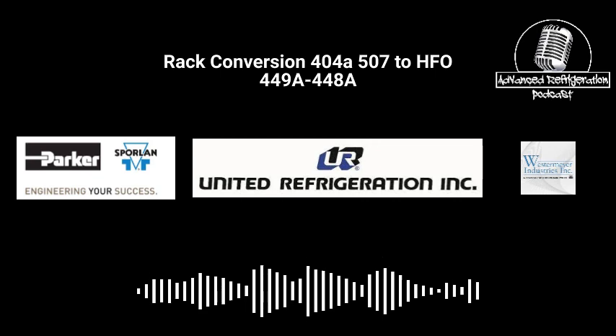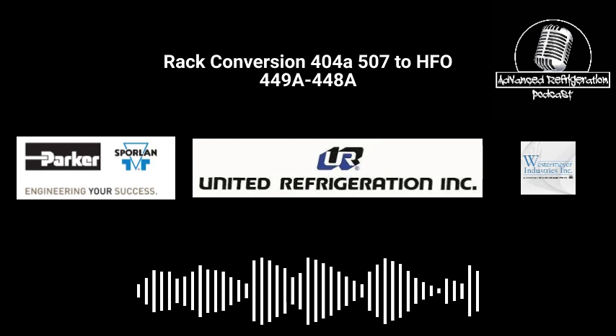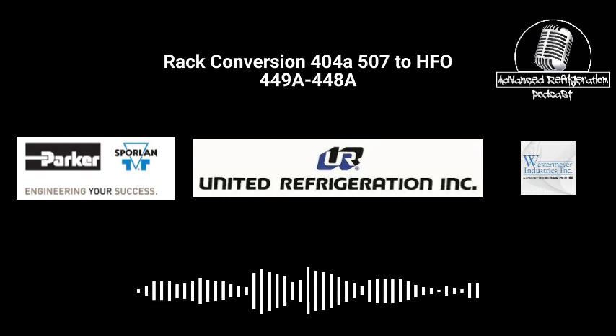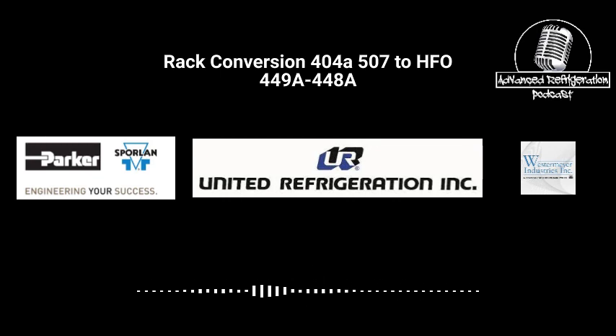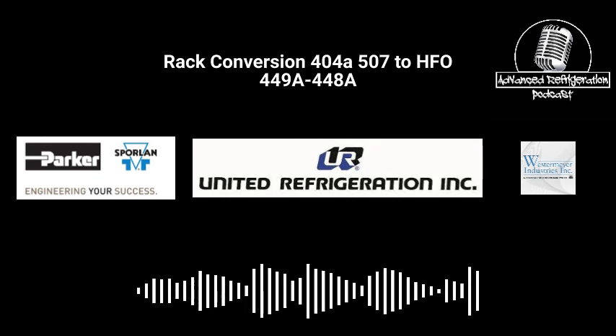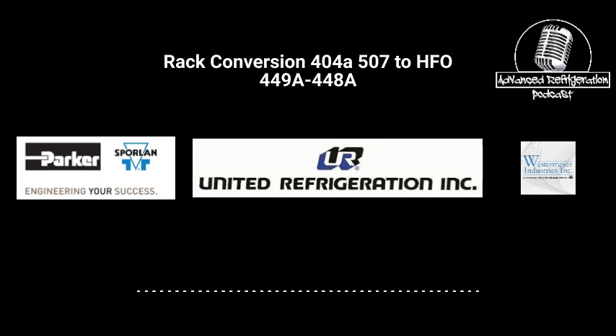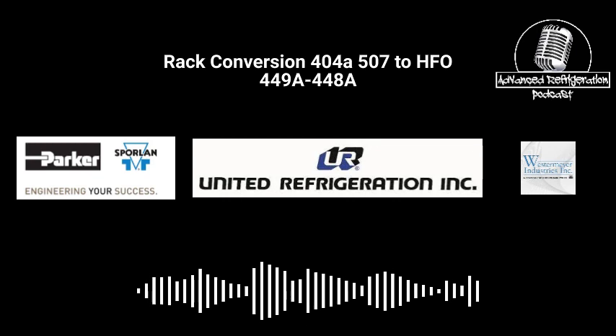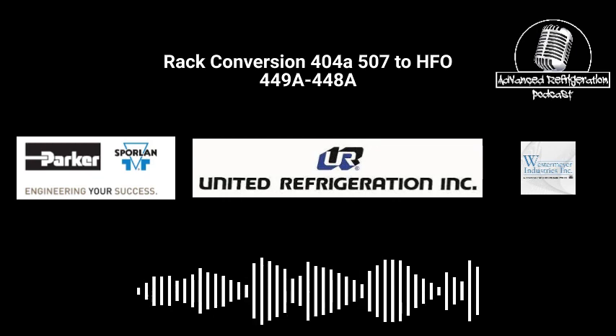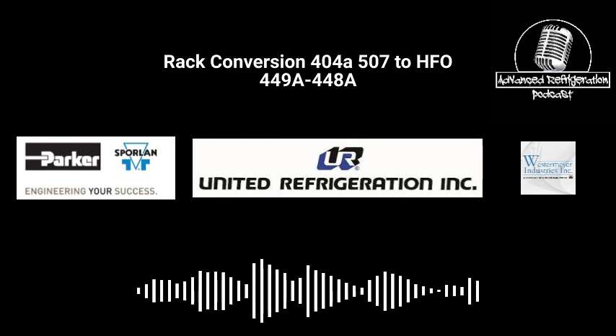Getting the power heads done before. I'm a big proponent of getting the power heads done before and then going back and setting superheats. Usually what we'll do is I'll let one of my guys do the changeover at night, and I'll come in the next morning and start running through superheats. I'll usually get there like 4 a.m. Those guys should be charged and running. I'm taking over, I get the rack smoothed out with a good charge in it, and then I'm going to start setting superheats.